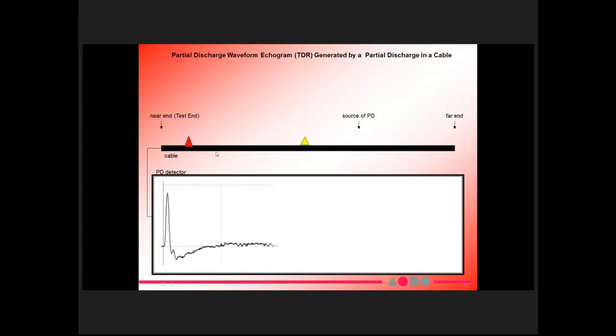And then, after a short while, that wave, which is the original pulse reflected off the far end, comes in as well. And the distance, basically, between this cursor over here and that second waveform over here, as you can see at the marker, is the distance between the far end and the source of your PD. So I'll just go through that one more time just for folks to have a look at it. By the way, when you look at this thing, we do slow it down just to try and highlight different events that take place. But in reality, this is one continuous movement at a constant velocity. That velocity is the velocity of propagation of the cable, which is typically around about 500 feet per microsecond. It changes slightly from one cable to another, but it doesn't slow down the way it's shown here. All right, so if you look at that, you get a fair idea of how PD transient takes place.